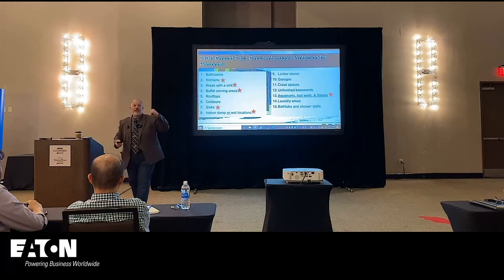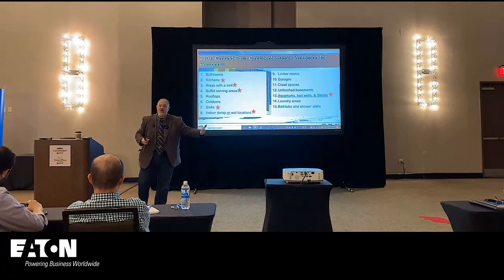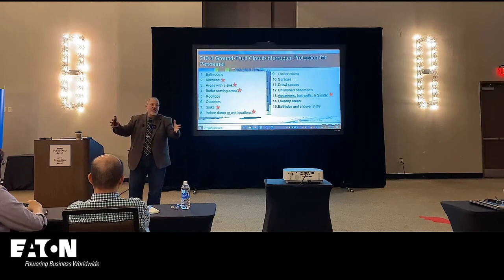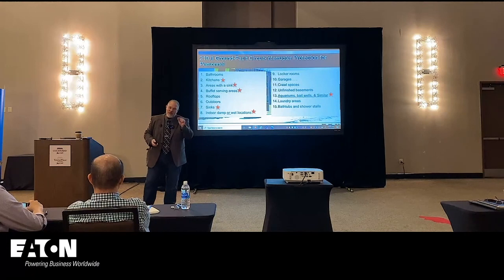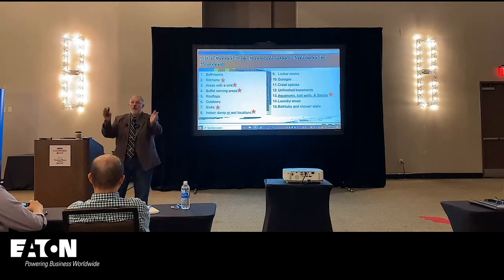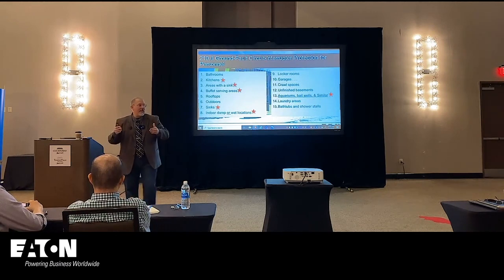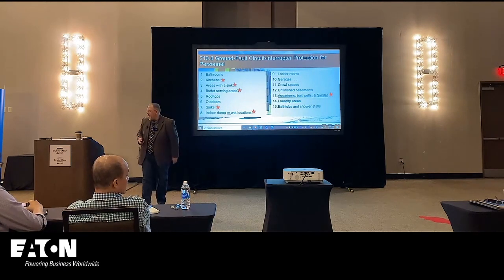So we made a change in 210.8A for dwelling units. It said if it's in a kitchen, I don't care. If it's in a kitchen and it's plugged in, you GFCI protect it. And if it's cord and plug connected, we added a 210.8D. But for other than dwelling units, we added a little bit different language. We said, look, if your appliance is within 6 feet of the sink, a permanently fixed or stationary appliance, not the receptacle, then you need to GFCI protect it. Okay, so we added that realizing that it's the appliance that's the hazard, not the receptacle.